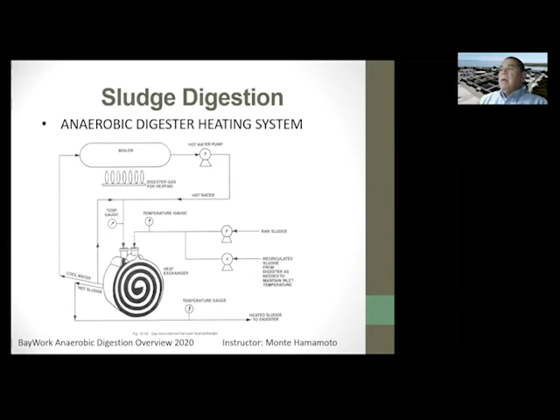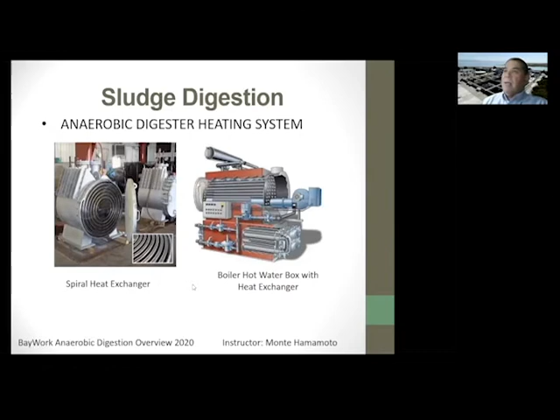And you can see this is a spiral heat exchanger with the rings we just showed you, and this is what it looks like on the inside. And then there's also another type where you have a big giant, like a hot water heater, that's like a big hot water bath, and then you run these sludge tubes through the hot water bath. This is a firebox that heats the hot water, and the hot waters are circulated around these tubes. Sludge is pumped in, goes through these tubes. They're very thin, and it'll transfer the heat. So that's how we can maintain that 95 degrees.